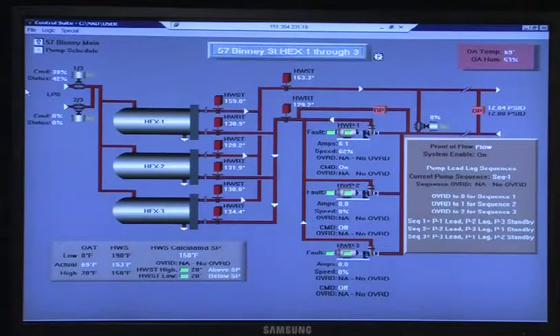And it goes through differential across the system. It's maintaining that differential, this valve right here. This valve and this pump speed are normally what'll get you the DP. So you go to the DP, when you max out your minimum, that's when you crack that. That would never happen, but yeah. And what ends up happening too is Charlie wanted to change a little bit of the sequence. If the lead pump is running and it can't bring the pressure up in the system, it will stage on a lag pump.